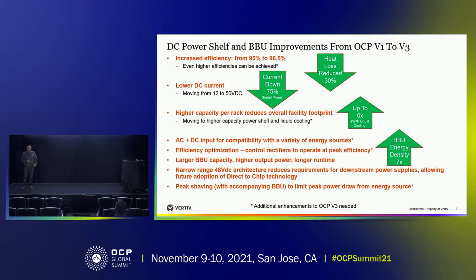There's energy optimization that can be had as well. As we all know, there are peaks during operation that may increase the usage of each server. If architected correctly, we're going to suggest implementing BBUs and battery technology that will also help the sustainability story, and growing the BBU size, maybe going to a higher runtime BBU. The idea of peak shaving is another alternative, where you'd use the battery backup and maybe cap the DC power shelf at a level that allows you to use both sources. Keep in mind those asterisk points are recommendations to build on the sustainability story.